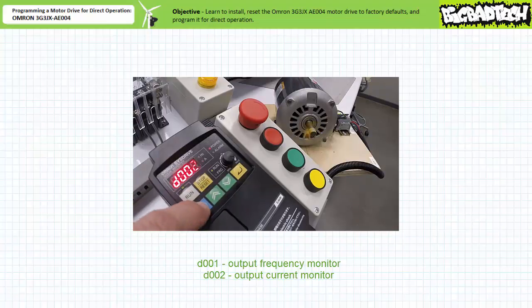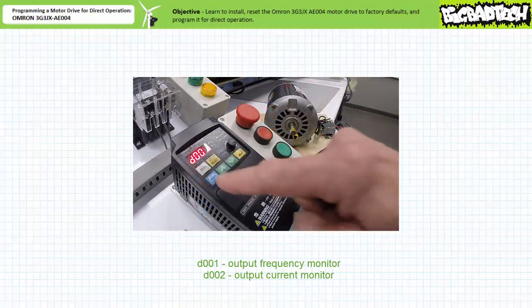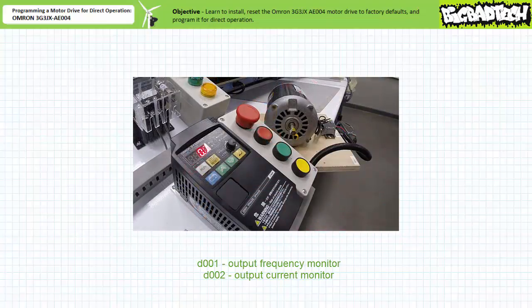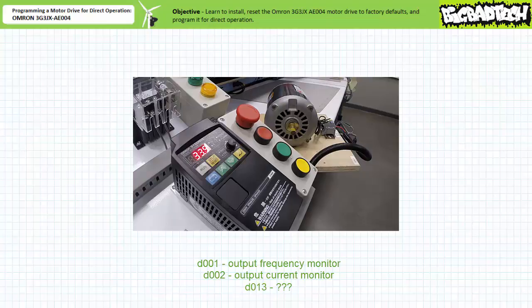While in operation, when we navigate to parameter D002 output current monitor, we find the unloaded motor is drawing roughly 1.2 amps. All right, here's your next challenge. Use the parameter list in the user's manual to interpret the data displayed when I navigate to parameter D013.